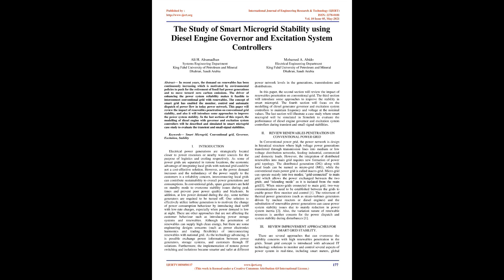The concept of smart grid has enabled the monitor, control, and automatic dispatch of power flow in today's power network. This paper will review the impact of renewables penetration on conventional grid stability, and also it will introduce some approaches to improve the power system stability. In the last sections of this report, the modeling of diesel engine with governor and excitation system controllers will be described and simulated in smart microgrid case study to evaluate the transient and small signal stabilities. Keywords: smart microgrid, conventional grid, governor, excitation, stability.